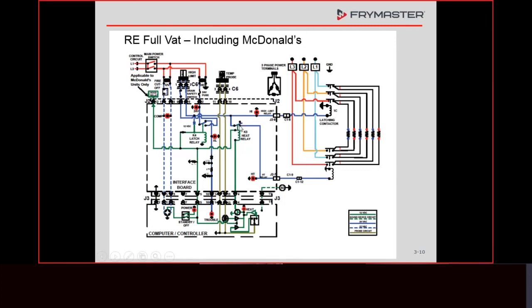That heat relay then is going to pull in and send voltage over to our heat contactor. That's when we're going to hear the other clunk. As soon as this equals this and it shuts off, then it's going to release. As soon as it drops down, or if it's sitting there idle, just on a timed fashion, it's going to cycle on and off. We drop product in there. We push the button, then drop product in there. That's the procedure we're supposed to do.